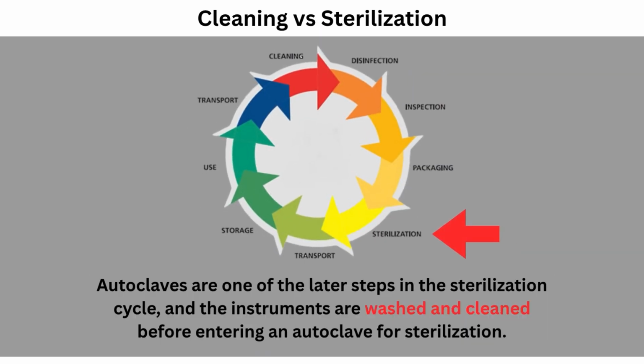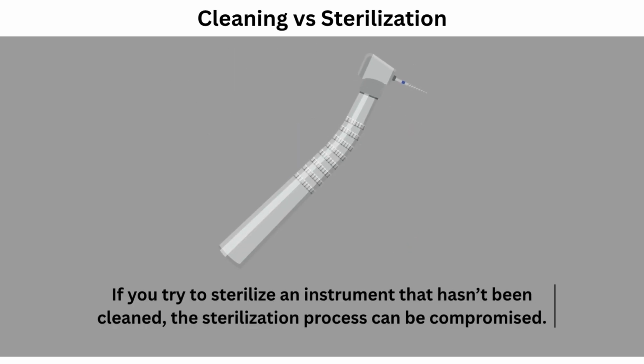Autoclaves are one of the later steps in the sterilization cycle, and the instruments are always washed and cleaned before entering an autoclave for sterilization. If you try to sterilize an instrument that hasn't been cleaned, the sterilization process can be compromised.